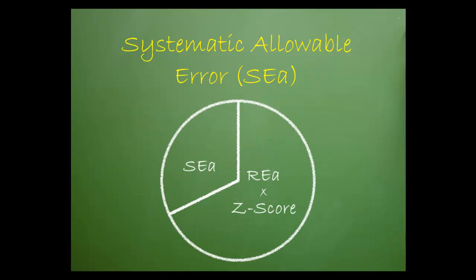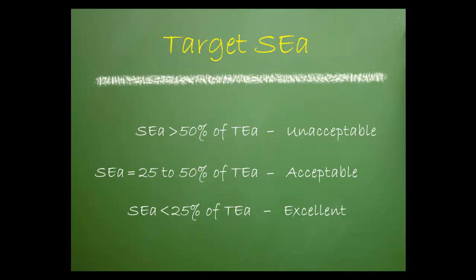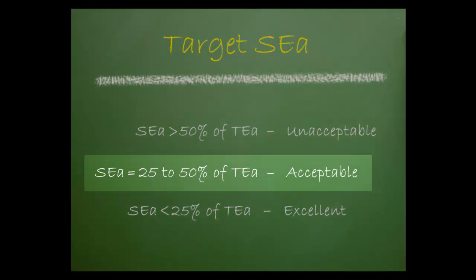Now that you understand the concept of systematic error, let's define systematic allowable error. SEA is a goal used to describe the accuracy at which a test system should be performing. SEA is one of two components of TEA, which laboratories use to designate quality specifications for clinical testing. One approach is to target SEA at 25 to 50% of TEA.